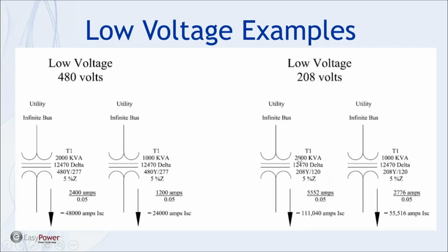Another nice thing when you get used to using per unit is when you have parallel transformers, I know I can just kind of picture this in my mind, adding a parallel 2000 or a parallel 1000. And it's just like from the AC circuits world, we just have two impedances that are in parallel. When you parallel impedances, they cut in half in terms of overall impedance. And so if we stuck with the 1000 kVA here, that available fault current then would double if you had truly parallel transformers, which I've only seen once in the work that I do.